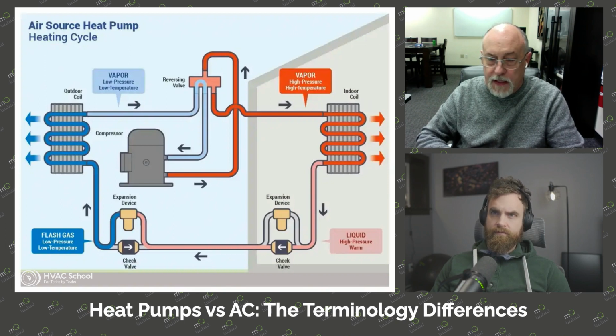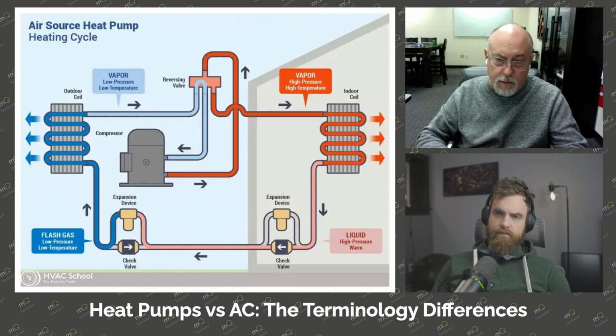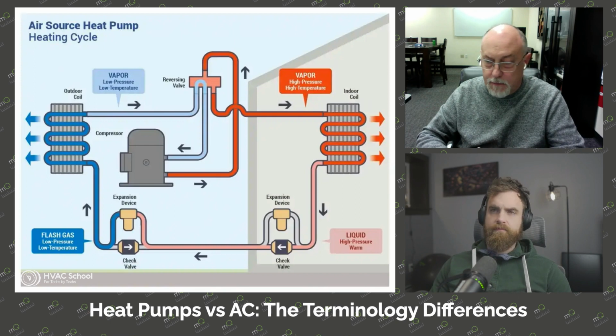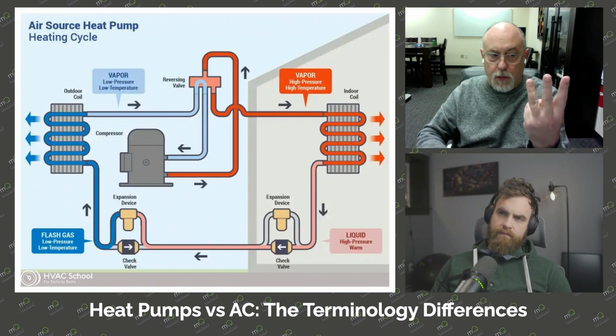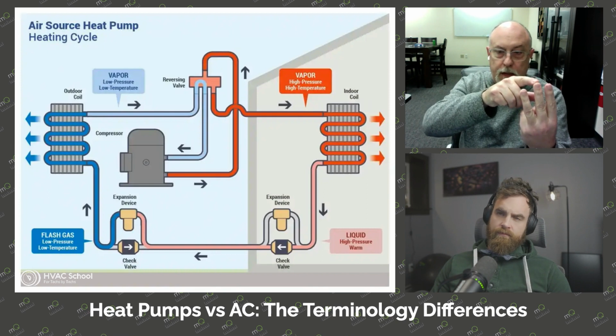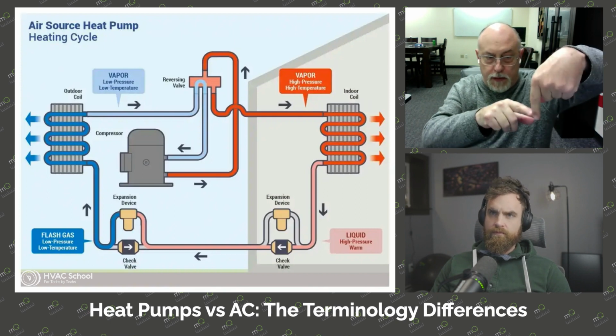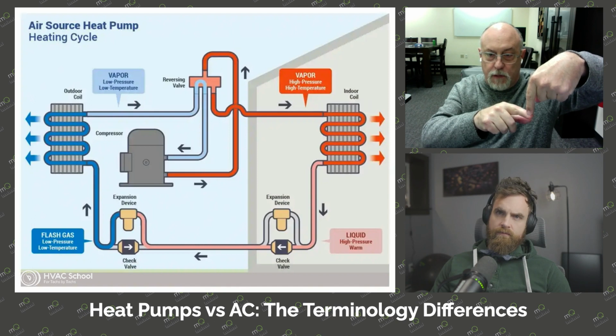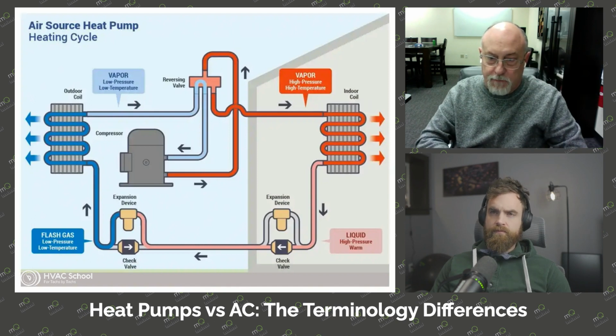Again, there's a true suction line on a heat pump. If you look at the middle port of your reversing valve, the middle port is always the true suction. It goes right into the accumulator or into the compressor, depending on whether you have an accumulator or not. If you think about it, there are three ports on top, and the center one is the suction line. Then the bottom port comes off, and that's always the discharge line. Always. On every reversing valve, it's always the same.